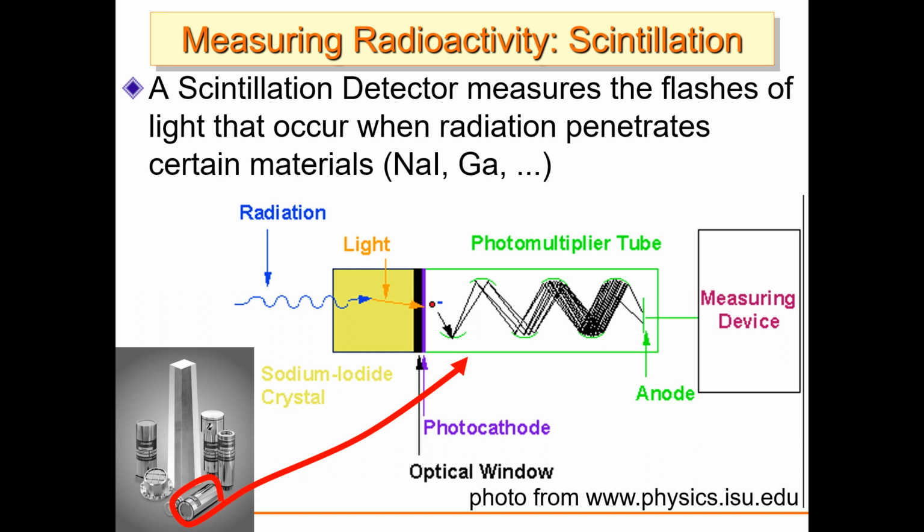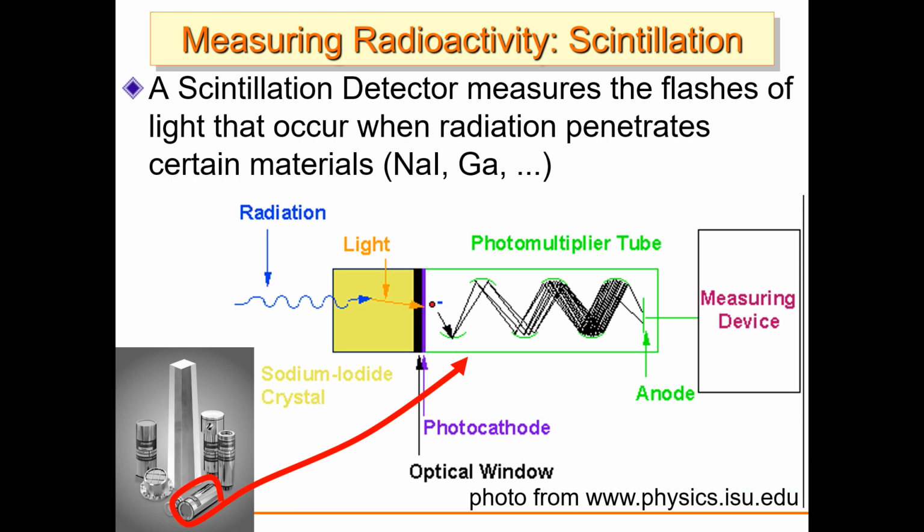They make really large ones and really small ones. The smallest ones are about this size. So you can have the little sodium iodide crystal in there and then a photomultiplier tube, and it's hooked to the counting device. So you see people walk around with the little thing that looks like an iron. This is the photomultiplier tube, and you're using that. They even make these on what look like floor cleaners. So the tube's facing down, and it's shielded on top, and it's a really heavy device.